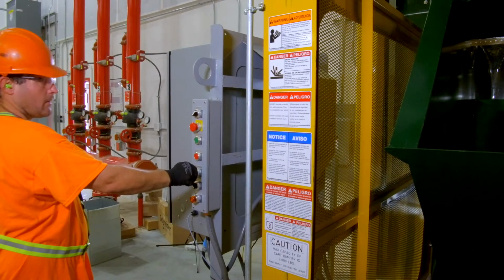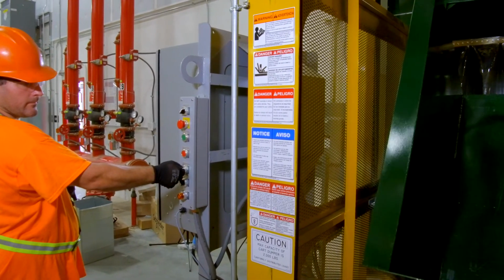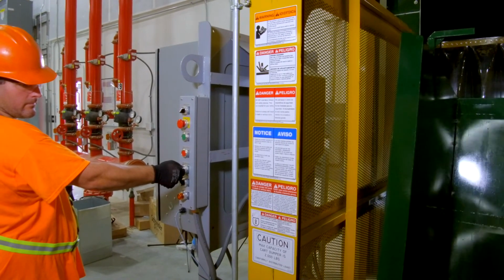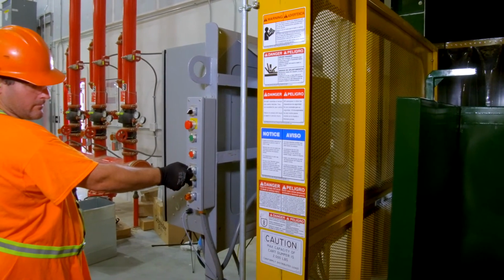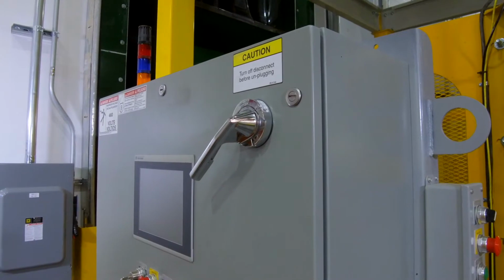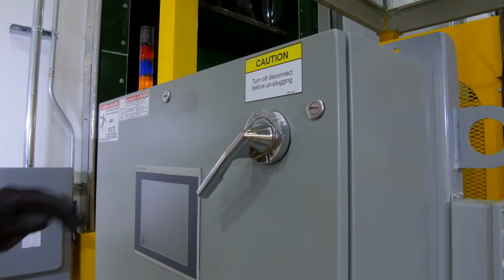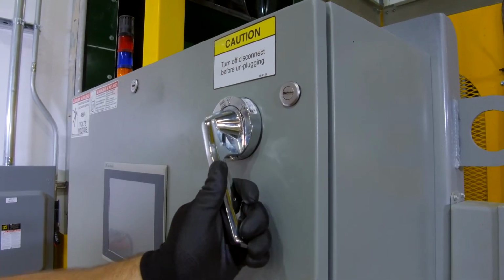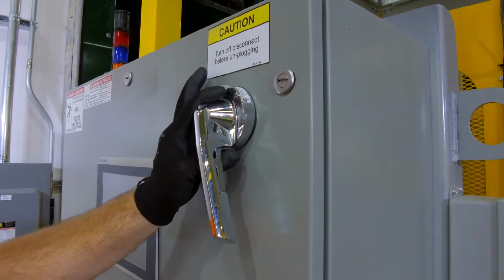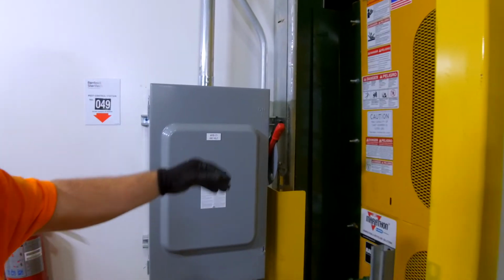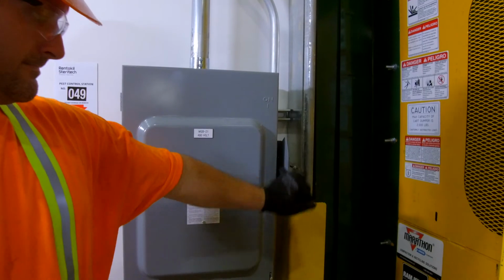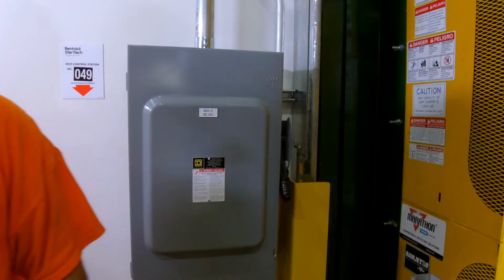Note: if any of the operating components have a risk of movement, lower them to a safe position or block them with appropriate equipment. Then deactivate the energy isolating devices so that the system is isolated from the energy sources. To do this, simply shut down all power sources and move the main disconnect lever to the off position.